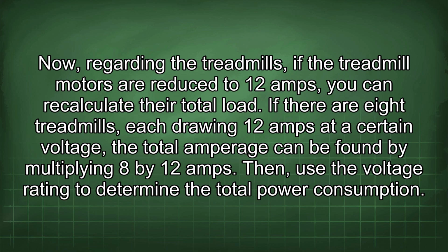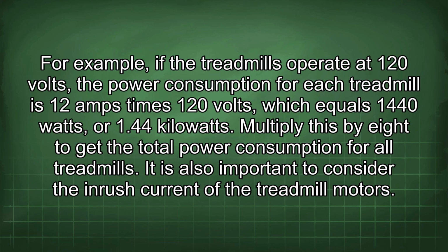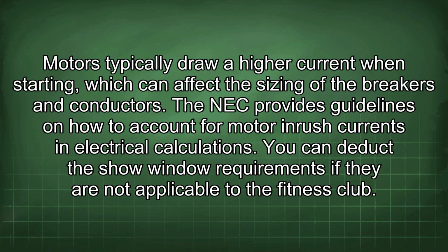Then, use the voltage rating to determine the total power consumption. For example, if the treadmills operate at 120 volts, the power consumption for each treadmill is 12 amps times 120 volts, which equals 1440 watts, or 1.44 kilowatts. Multiply this by 8 to get the total power consumption for all treadmills. It is also important to consider the inrush current of the treadmill motors. Motors typically draw a higher current when starting, which can affect the sizing of the breakers and conductors.